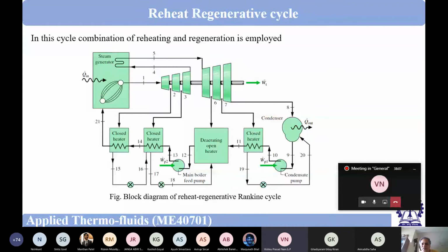And in a practical power plant, there are so many things. What kind of size of the heat exchanger? These are all heat exchangers. What kind of size, and whether there are other equipment you have to place. So those different issues are there, and the selection depends on these, and I am just raising one thermodynamic issue. For other closed feed water heaters it will not be a problem, but for a closed heater just after the condenser, it is thermodynamically not good. Alternate design can be done. All right? Yes, sir.